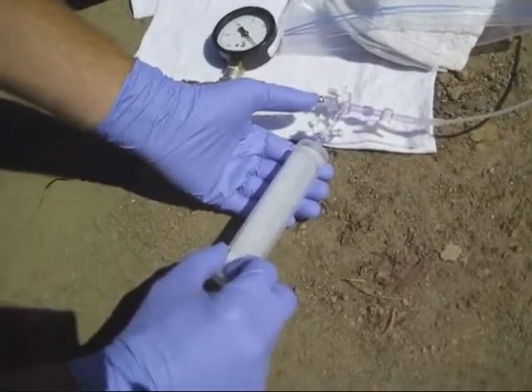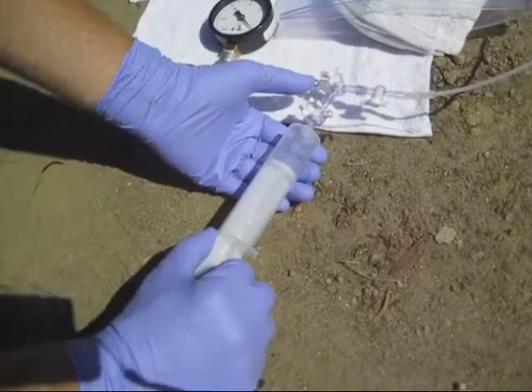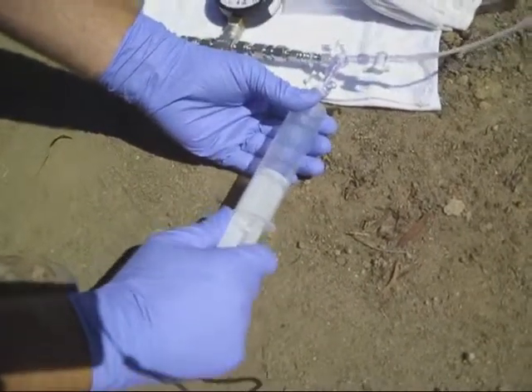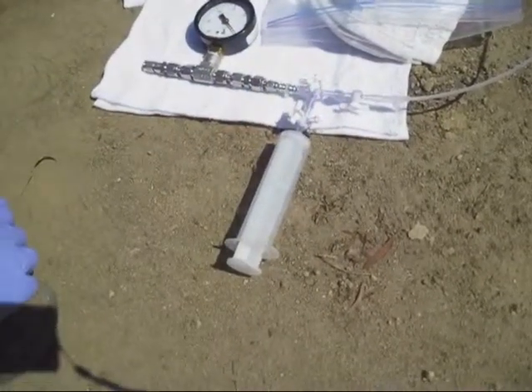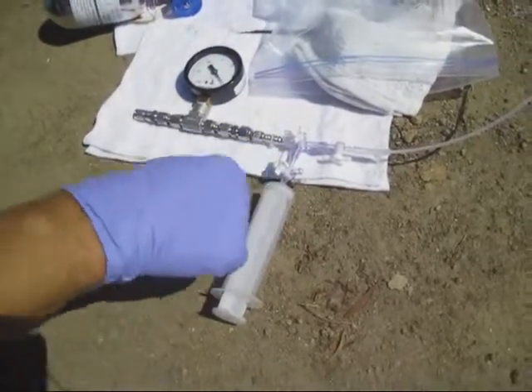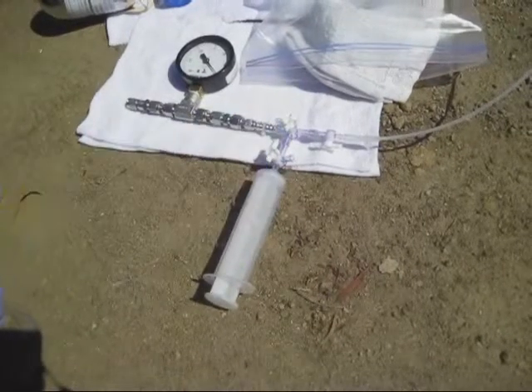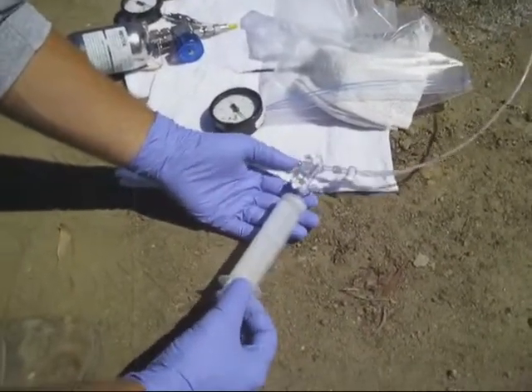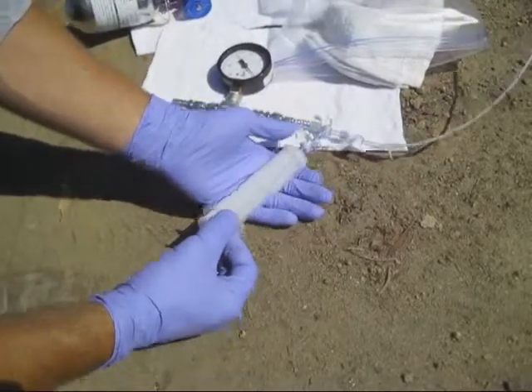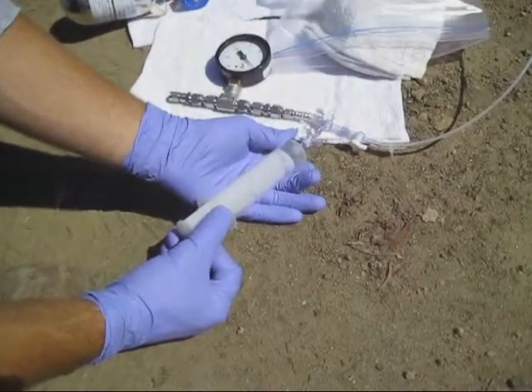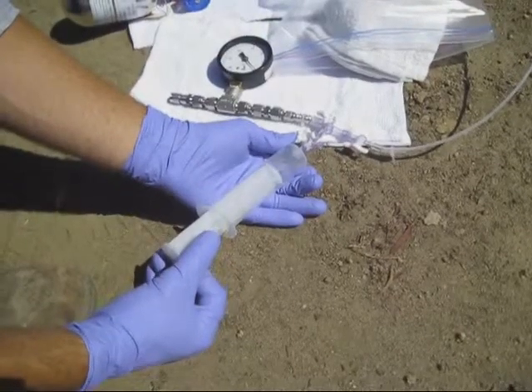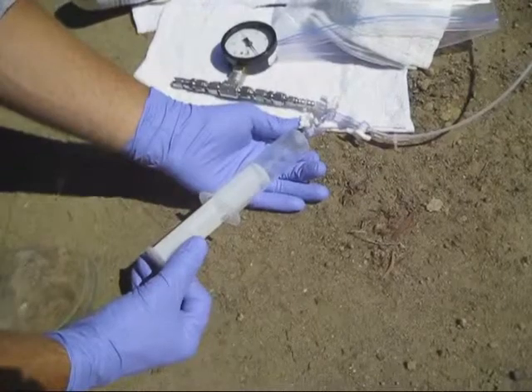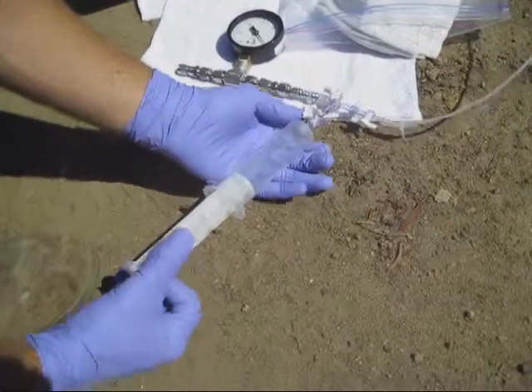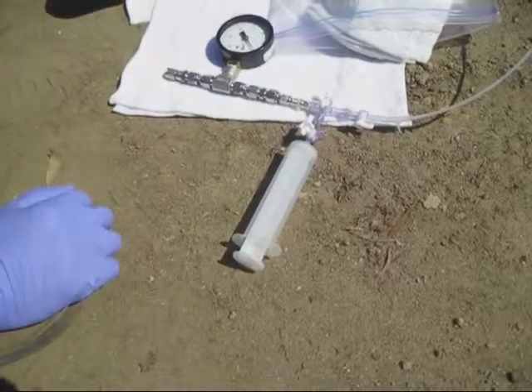So we can simply draw back on our syringe. This is a 60 milliliter syringe. And you just draw the sample into the syringe, switch your valve, evacuate the syringe, continuing to pump out your calculated purge volume. If you have larger purge volumes, you could connect a pump here and pump out the appropriate purge volume as well. One of the benefits of using a syringe to sample is you can regulate the flow rate of the probe. This is a 60 milliliter syringe, so I know if I pull the plunger back and fill the 60 mils in about 18 seconds, that's going to put me at about 200 milliliters per minute. Draw back and evacuate.